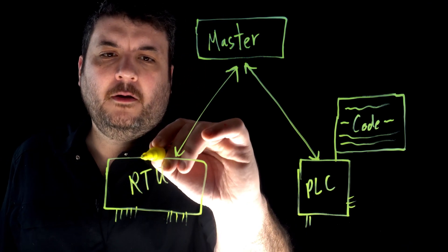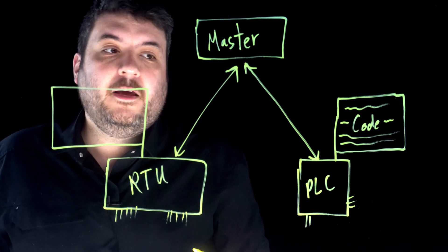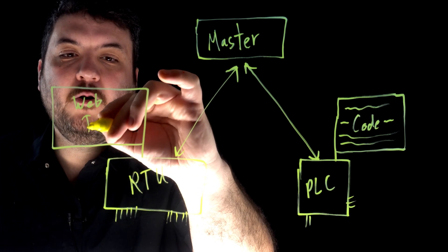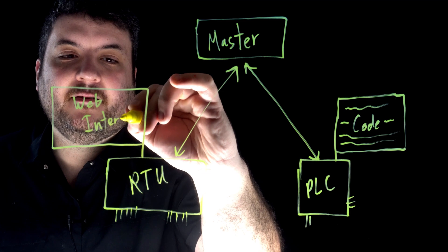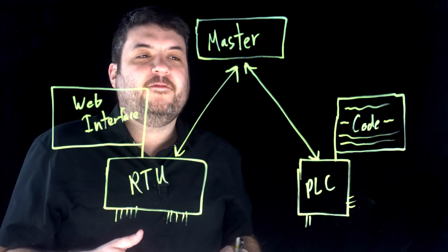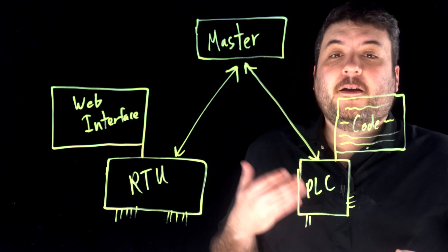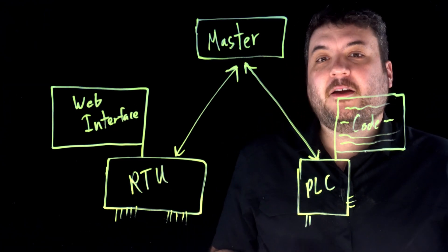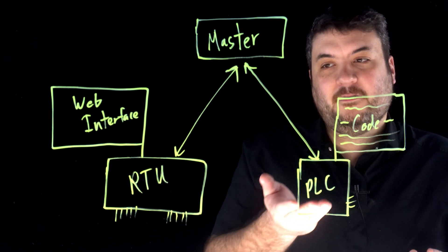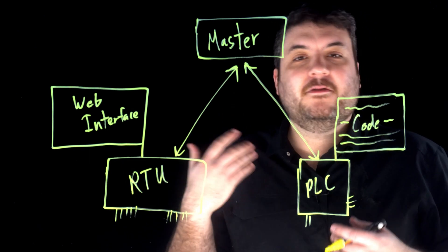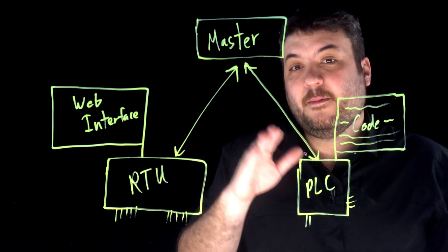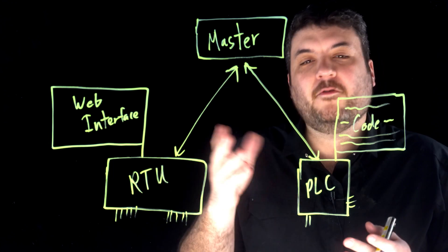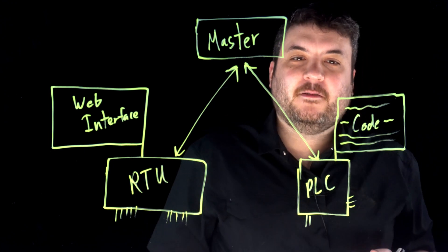The difference with an RTU — at least the way we build ours at DPS and the way many in the industry do it — is to have more of a web interface. If you've ever set up a home router or any kind of network-enabled device with a simple built-in web interface, you know how this works. You're configuring things, setting things up, filling out fields — you're not writing code from scratch. That means you don't have to hire a specialist to write a programming language for the device. You can just get into the web interface and tell it: use this IP address, here's how I want you to react, here are the names of your 32 inputs — smoke detector, door, high fuel sensor, whatever you've got. You're configuring and provisioning as opposed to straight programming.